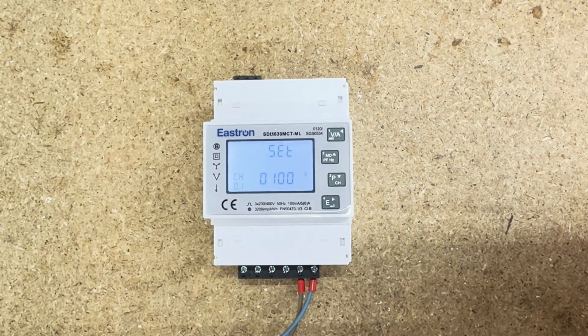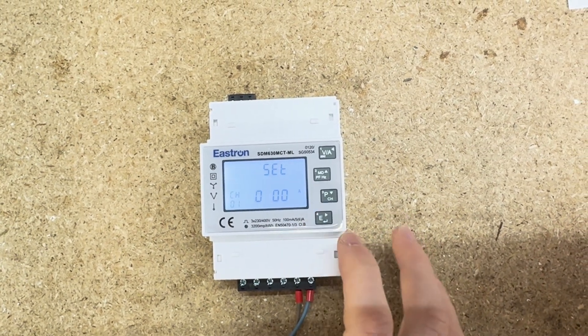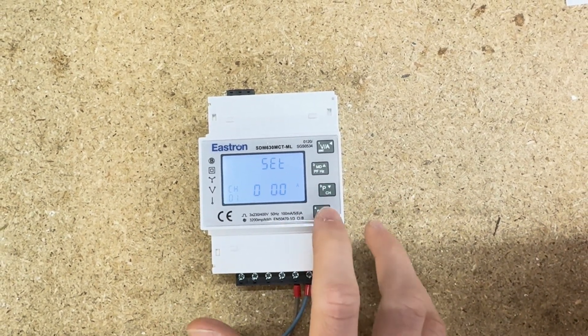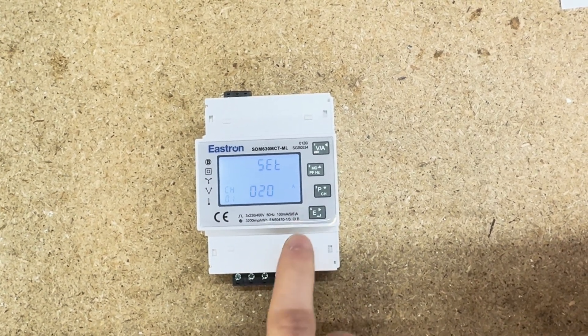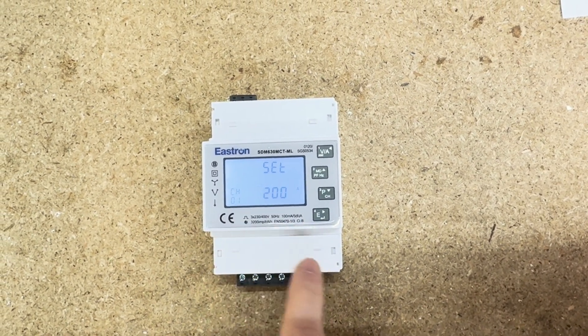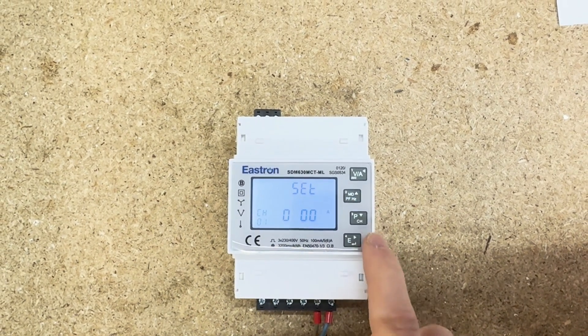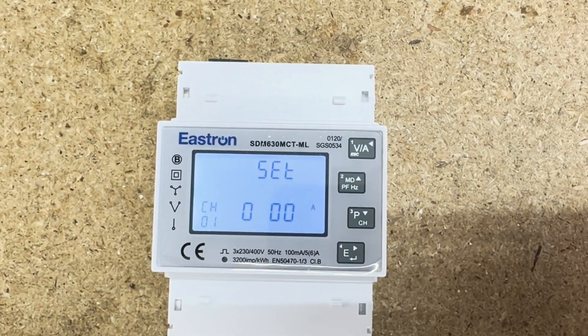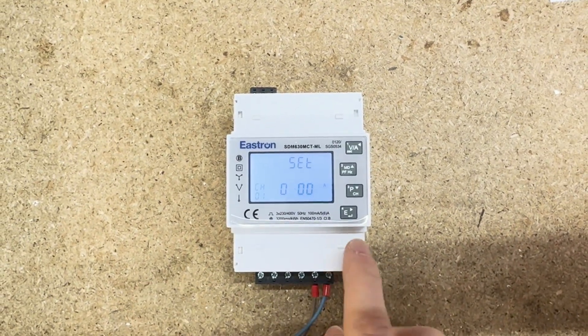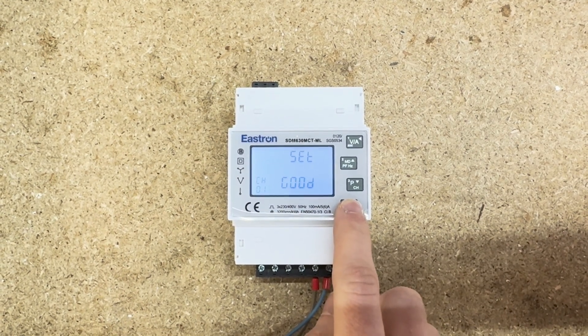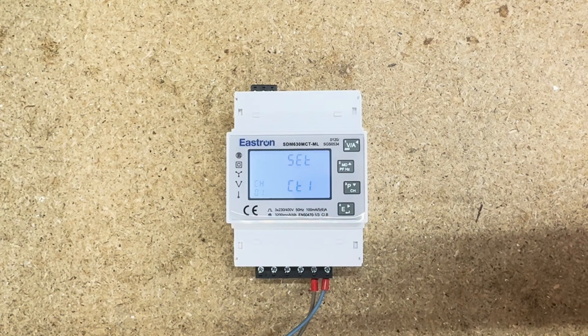Then we've got the option to set the meter. It's currently set to 100 amps as default, so we want to change it to 200 amp. The E button, if you just tap it, allows you to go to the next digit — you can see the digit that's flashing. Tap it to go through to the next one, and the up and down arrows — either MD or P — will allow you to change the digits up and down. I've got 200 there, so now I'm just going to press and hold E. You can see that says 'good', so that's now set at 200 amp to 100 milliamp.